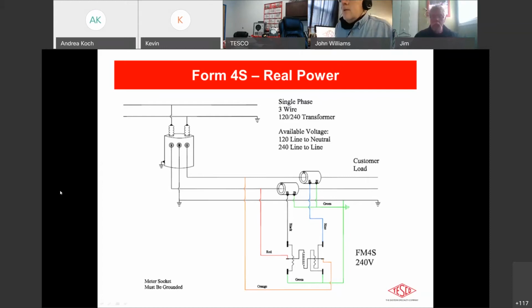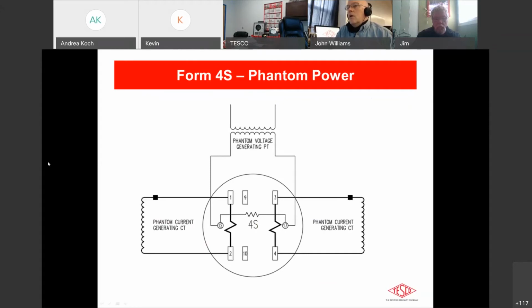Okay. Thanks, Kevin. So again, you see the similarities between the 4S transformer rated meter form here and the 2S self-contained. This again is for higher power situations like Kevin mentioned. Again, here we do the same thing in testing the meter. We put the potential transformer across the voltage coil and use two current sources to put the current to the meter. Again, a lot of these are going to be repetitive as far as the application, and just know that the different situations for current directions and so forth, you'll get to like Z coils later. Those are all simulated using the software.